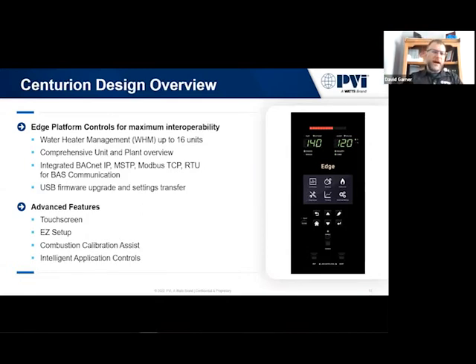One thing I really like to highlight is straight out of the box, you don't need a proto node. You can connect to it with BACnet MSTP, IP, Modbus, all the standard protocols. It's extremely simple: you land your wires on the terminal strip, go into the controller and say, here's what protocol I want. It identifies that, it will find the server. You can confirm the MAC and IP address of that server.